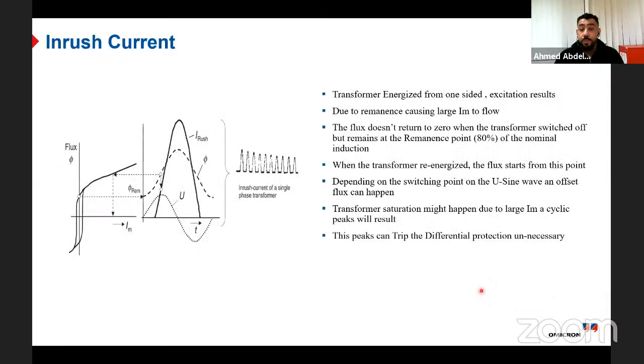Another phenomenon which is very important for us to understand is the inrush current. What is the inrush current? The inrush current happens if I'm trying to energize a transformer. What is the procedure? The procedure is I will keep the low voltage side open, and I energize the transformer from the high voltage side, because it's not common practice to energize the high voltage side on a closed circuit breaker on the low voltage side, because this will lead to a huge current flowing suddenly.